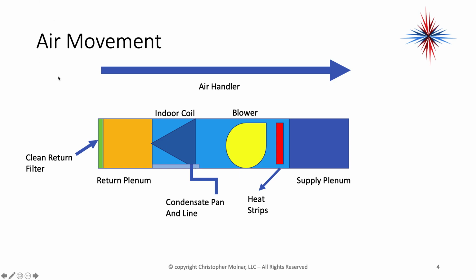So this is what makes up our air handler in a horizontal mode. The air, most often, 99% of the time, moves from the return plenum through the indoor coil, through the blower, across the heat strips, and out the supply plenum. Now, in some older systems, the indoor coil and the heat strips may all be on what I call the supply side or the positive side of the system. But 99.9% of the time right now, it's this setup. Under the coil, we have a condensate pan and line, so we have to get rid of the moisture off the coil.